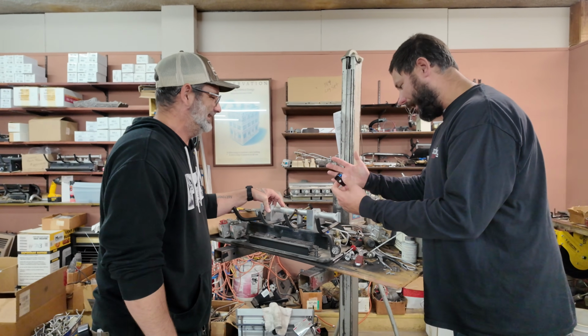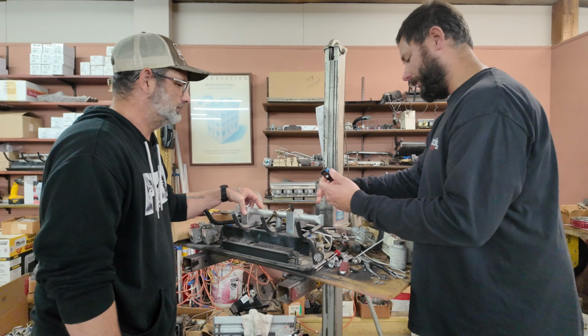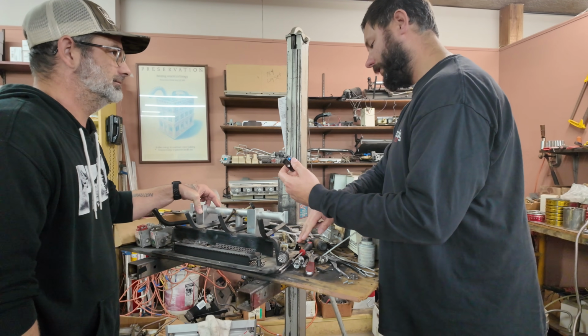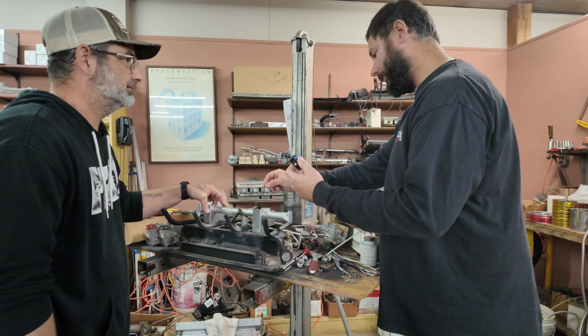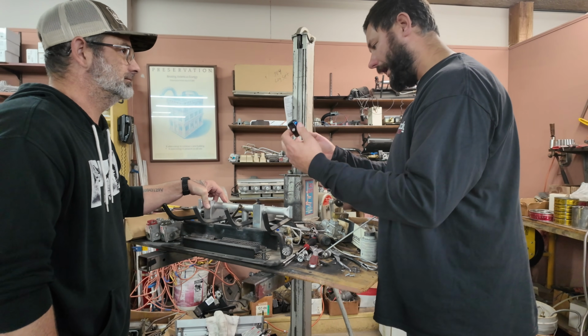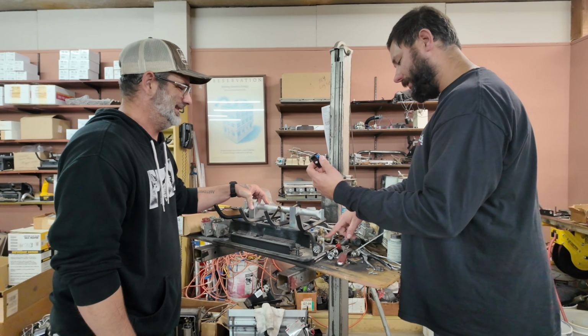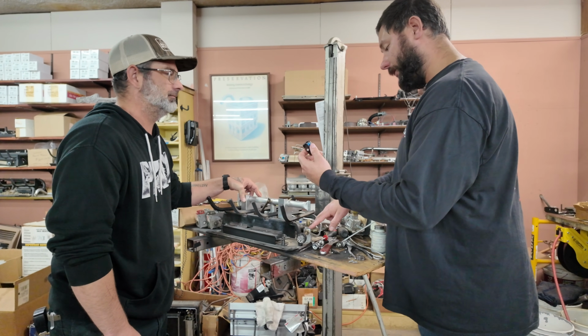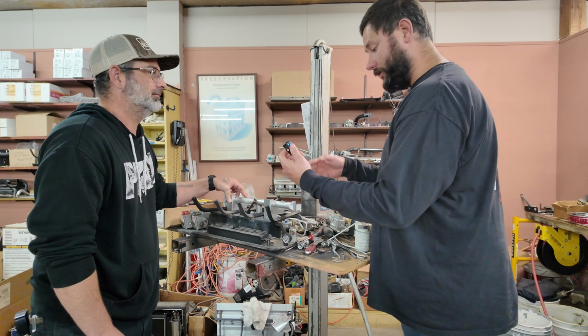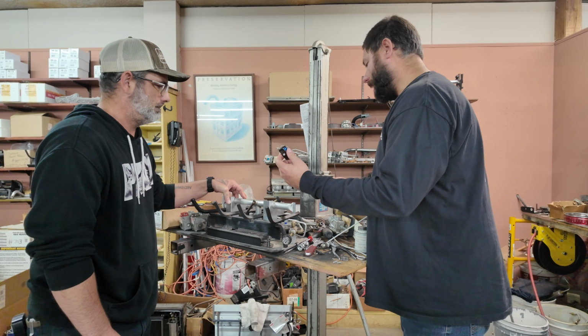All right, so recap again: bad thermocouple, weakened thermocouple, dirty pilot assembly. Operator error, not holding the pilot valve in long enough so that the thermocouple gets heated up and sends a signal back to the pilot valve, letting it know that we have gas, we have flame. We're good to go. Yep. And then there is not knowing that you cannot turn this back on, and it won't really function if it's overheated or hot. Still hot. Okay, got it.